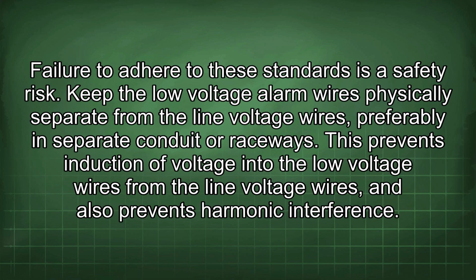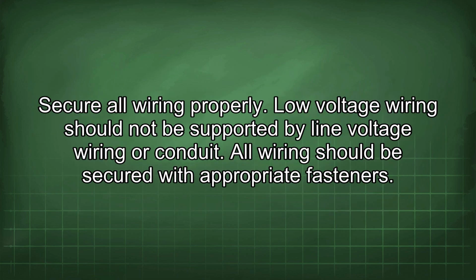Keep the low-voltage alarm wires physically separate from the line-voltage wires, preferably in separate conduit or raceways. This prevents induction of voltage into the low-voltage wires from the line-voltage wires, and also prevents harmonic interference. Secure all wiring properly. Low-voltage wiring should not be supported by line-voltage wiring or conduit. All wiring should be secured with appropriate fasteners.